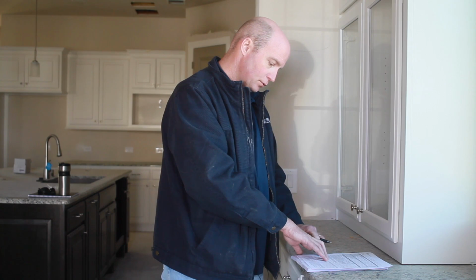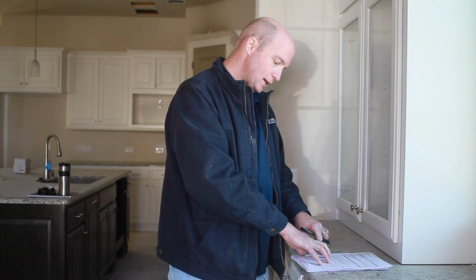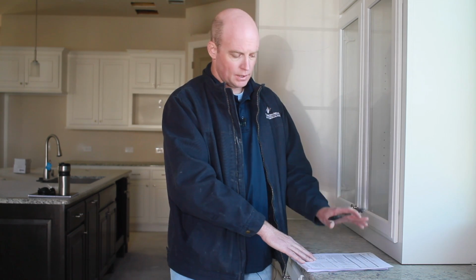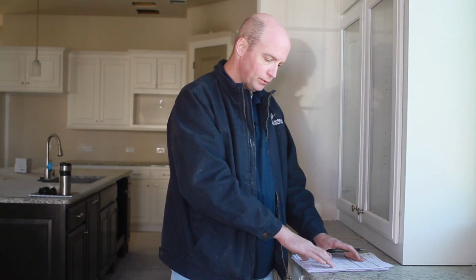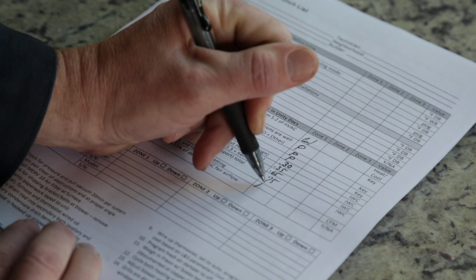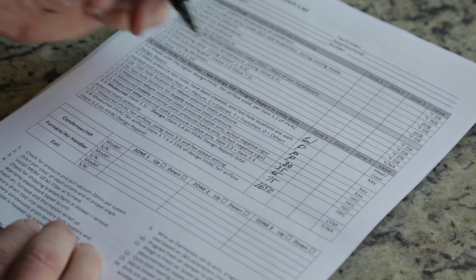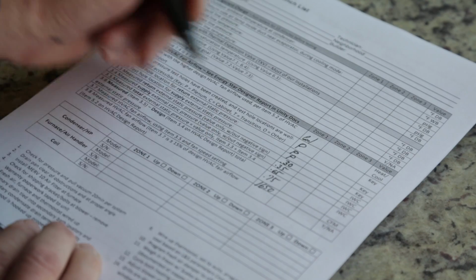Then line 3.7, measured fan airflow. Well, with that external static pressure on that speed setting, we looked up in a blower table, and it told us we were running approximately 1,650 CFM. Item 3.8, the measured airflow. Was it within 10 or 15% plus or minus of the designed airflow? Well, this was a 3.5-ton system. We're at 1,650 CFM. We're a little on the high side, but we're there.